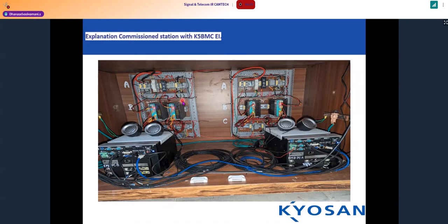And this is the operator video wiring information. There will be two different embedded PCs as per the audio. The two embedded PCs will be powered up with different DC-DC converters. So for the system operator video A will have a separate DC-DC converter. For this, a separate 110 volt DC will come.